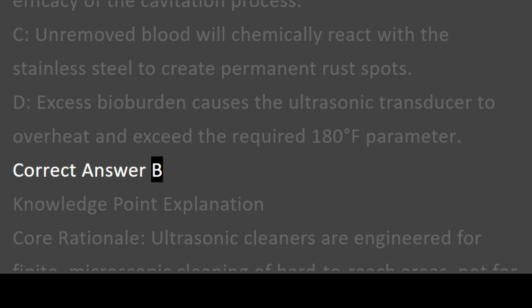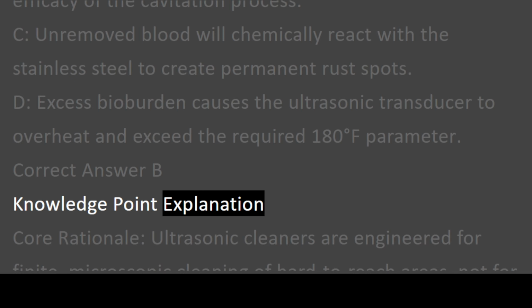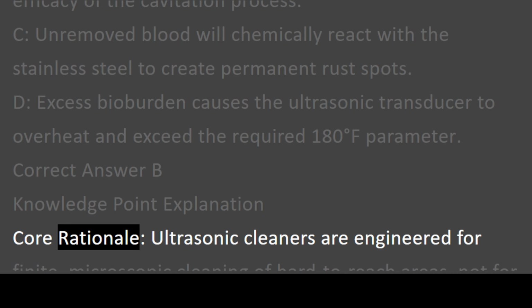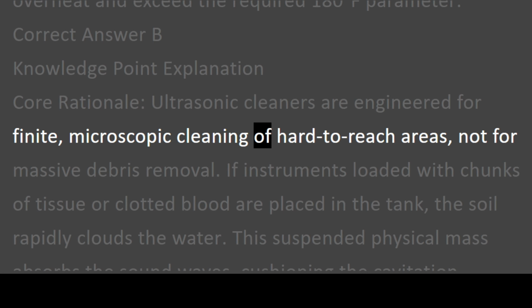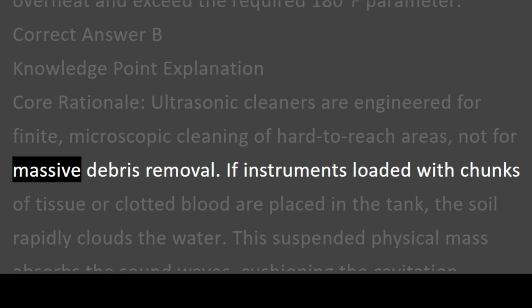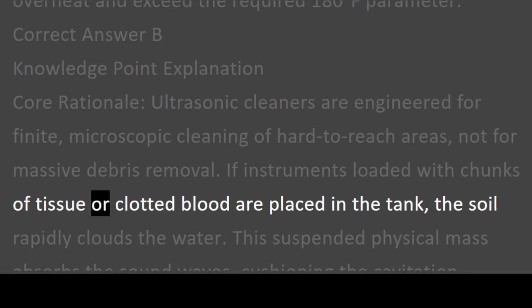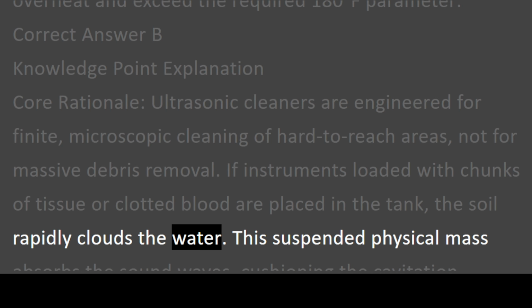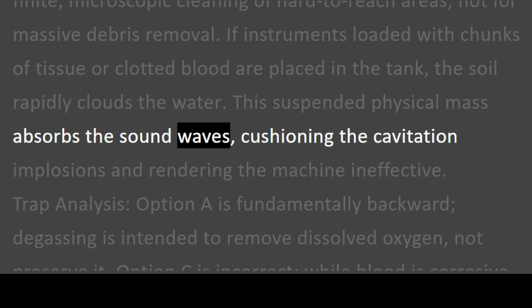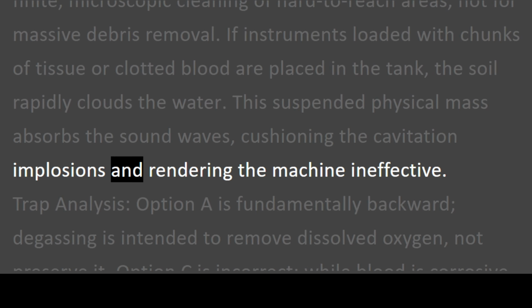Correct answer B. Knowledge point explanation. Core rationale. Ultrasonic cleaners are engineered for finite, microscopic cleaning of hard-to-reach areas, not for massive debris removal. If instruments loaded with chunks of tissue or clotted blood are placed in the tank, the soil rapidly clouds the water. This suspended physical mass absorbs the sound waves, cushioning the cavitation implosions and rendering the machine ineffective.